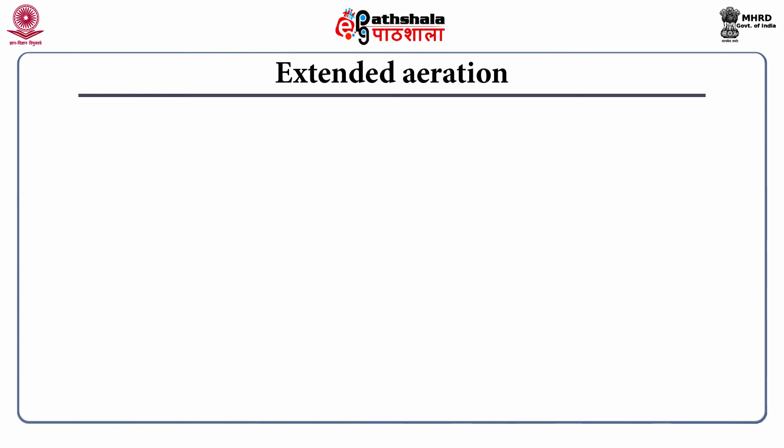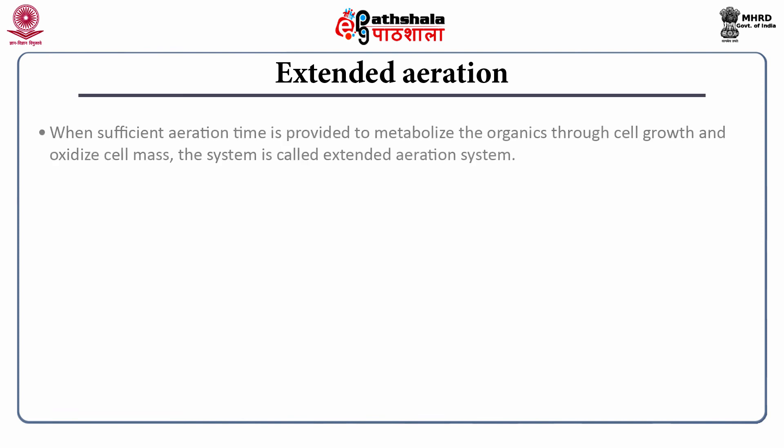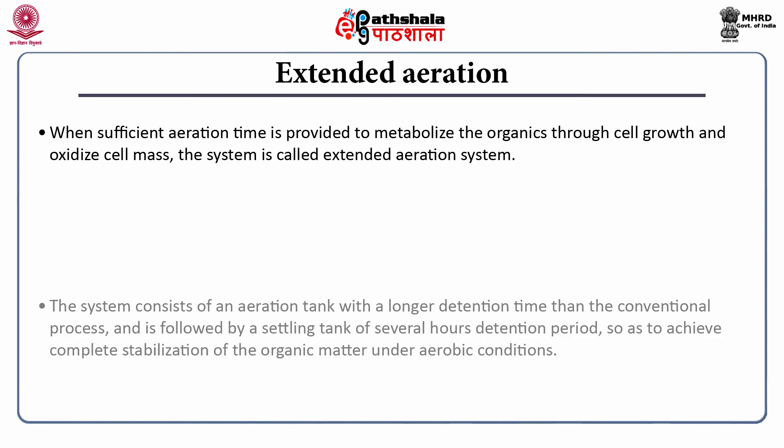Another variation is extended aeration. When sufficient aeration time is provided to metabolize the organics through cell growth and oxidize cell mass, the system is called an extended aeration system. It consists of an aeration tank with a longer detention time than the conventional process, followed by a settling tank of several hours detention period, so as to achieve complete stabilization of the organic matter under aerobic conditions.